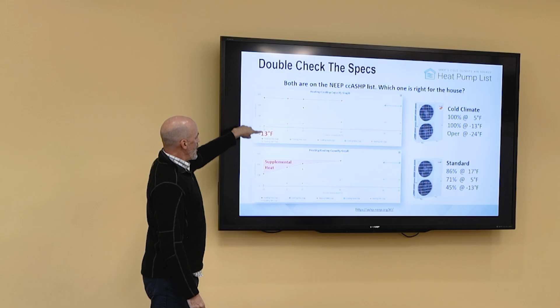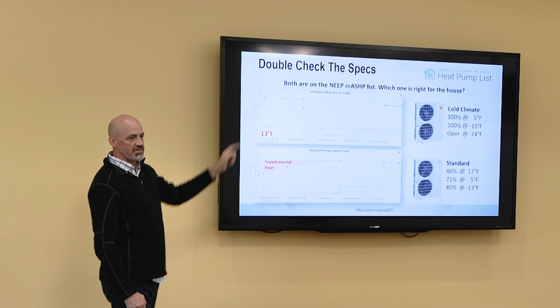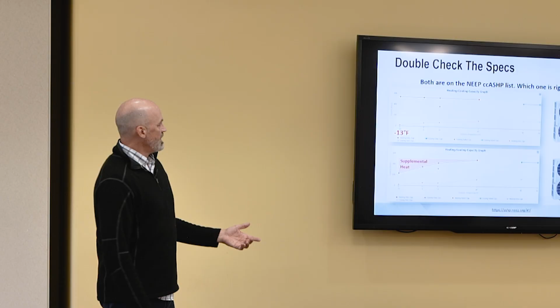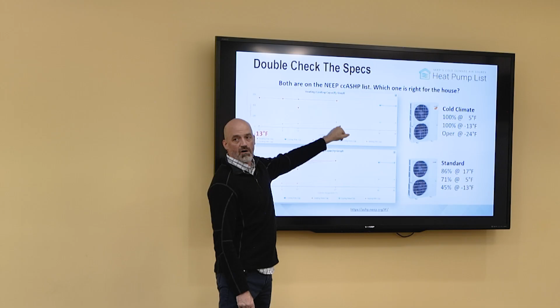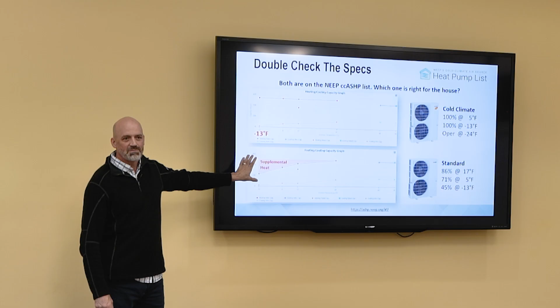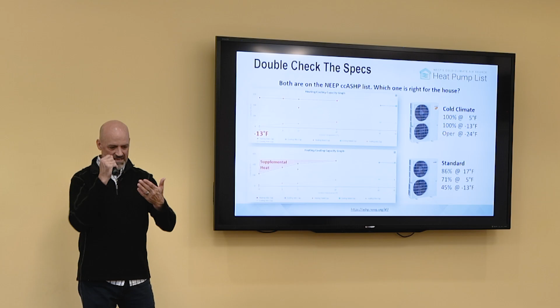The top one is 100% capacity at -13. That's what new equipment is capable of. It will deliver 100% rated capacity at -13. It's getting better and better and better. And really good minimum turndowns, so in the spring and the fall when you have part load conditions, you've got good operational efficiency. This other one that is a couple digits off needs a lot of supplemental heat. This right here, improperly selected and installed, upsets people a lot, right? This is what gets the builder in trouble, the installer in trouble, the code official for saying, yes, this is okay. This is why they ask for this information to say, yes, this looks right to me.